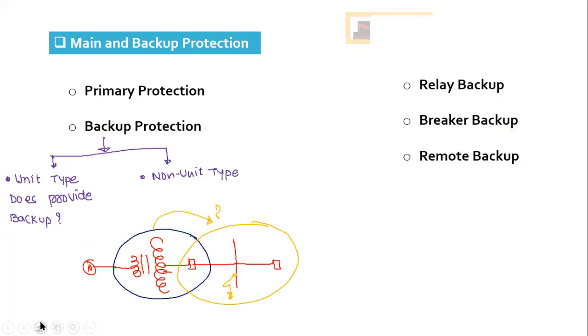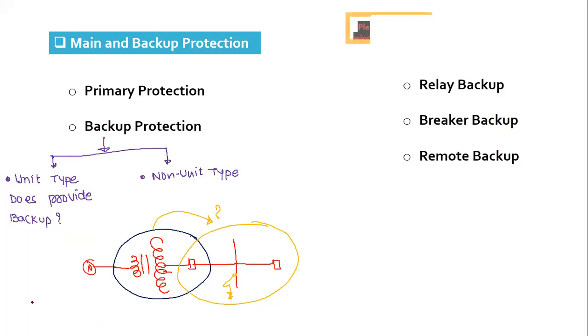It is a unit protection scheme. Correct, Niti, your answer is correct. Yes or no, what do you think? Yes, Bhavesh, correct. Because this is unit protection, it will not operate outside its zone of protection, it will never operate anywhere outside it. So obviously for this fault it will never operate, so it will not provide backup.